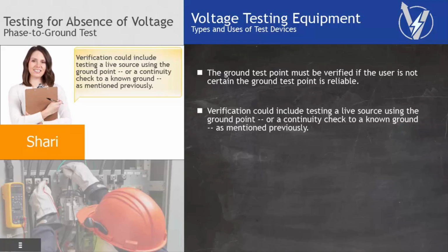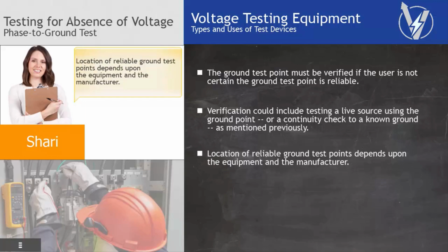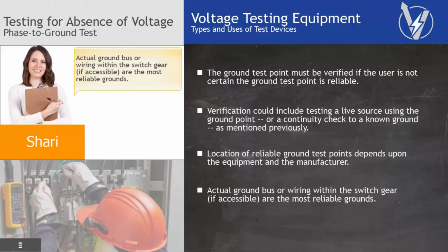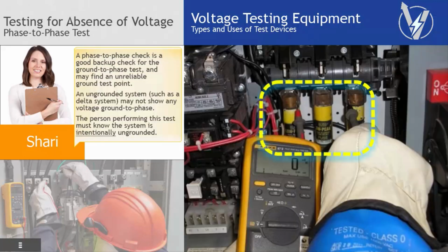Verification could include testing a live source using the ground point or a continuity check to a known ground, as mentioned previously. Location of reliable ground test points depend upon the equipment and the manufacturer. Actual ground bus or wiring within the switchgear, if accessible, are the most reliable grounds. A phase-to-phase check is a good backup check for the ground-to-phase test and may find an unreliable ground test point.